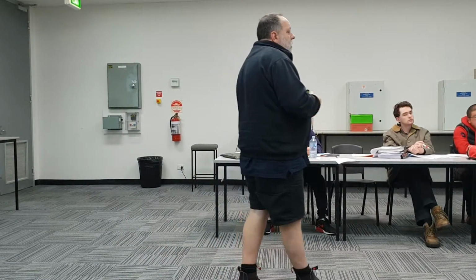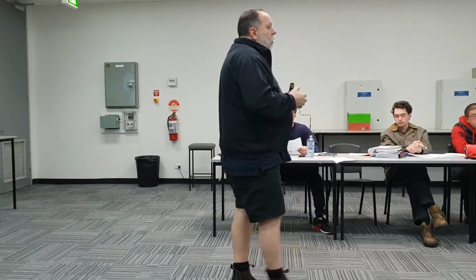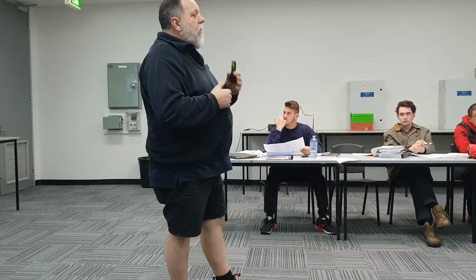If you've got, say, 3 20 amp outlets, divide that by 3, it would be 1 20 amp outlet per phase. And then it might say 50% of the load, so you times it by 0.5. So we'll work on those, have a look through the exercises as you go through, make sure you understand where you're going to divide them up across the phases.